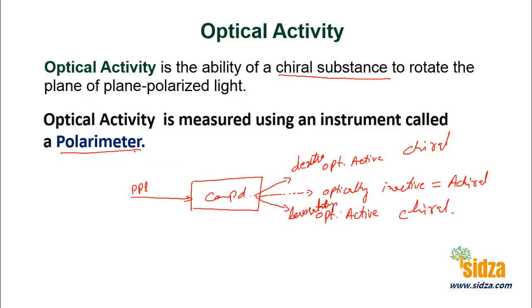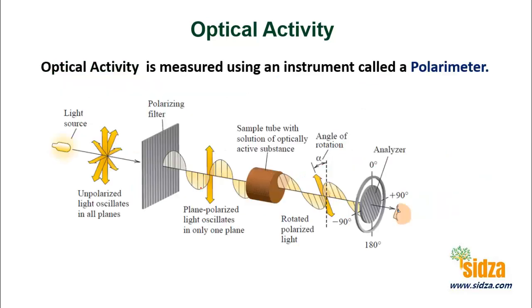The instrument we use for measuring optical activity is called a polarimeter. We have a source of light — ordinary light is unpolarized because it oscillates in all planes, with electric and magnetic fields oscillating in all planes. When you pass it through a polarizing filter, a plane polarized light oscillates only in one plane. When we pass this PPL light through a solution which is optically active — contained in a sample tube — and observe it through the analyzer, there will be some rotation, either in the right direction or in the left direction.